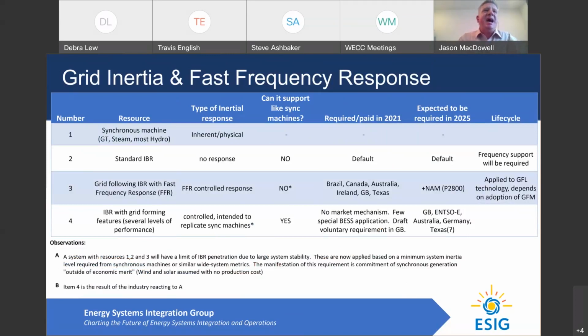Synchronous machines, as Debbie pointed out, have an inherent physical response because they're synchronized to the grid. If there's an instantaneous change in frequency due to loss of generation or a large load, the frequency moves around, and the inertia of a synchronous machine couples directly to the grid through its synchronizing torque. A drivetrain in motion stays in motion.